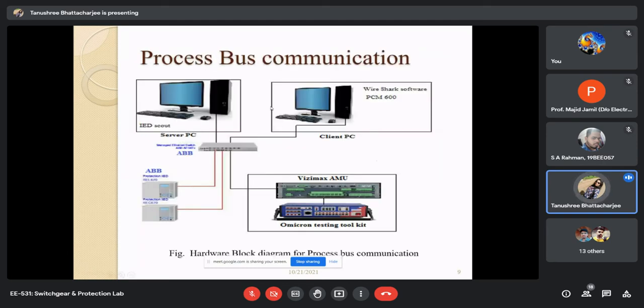Now this is process bus communication, the process level and bay level communication, which we have installed in the lab. There we have two IEDs, both from ABB, and one merging unit from a separate vendor. Then Omicron is the testing kit. Here Omicron will only inject the V and I value, because we have not connected it to a live substation.